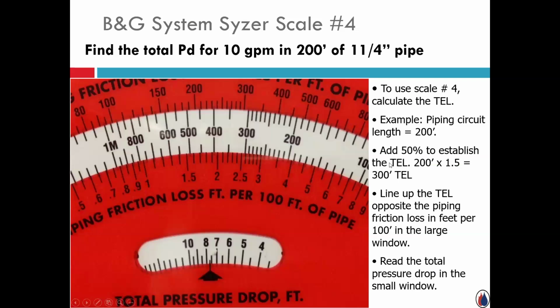So just, again, a silly little example, but what we found from scale 2 before is we needed 1.25 inch pipe for 10 gallons a minute flowing through copper pipe. And in the example, they said, hey, we've actually got 200 feet of pipe in this building for this example for 100,000 BTUs. So to use scale 4, you get 200 feet, but you have to account for the fittings. So I'm going to use that rule of thumb in this case. I'm going to add 50%. So I'm going to say I have a TEL of 300 feet.